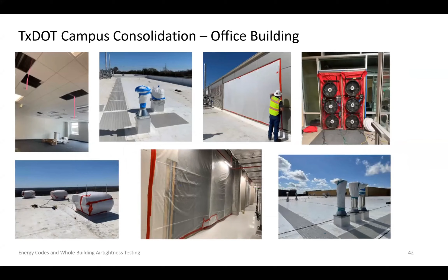So this is one where originally it was going to be divided into two zones, a zone A and B and a zone C. What had changed from the original bid documents we'd been given to prepare, compared to the as-constructed conditions, was that they had a huge pass-through on each one of these floors. So we had to do a bit of scrambling, but we already had sufficient fans on site, so we could pressurize this entire building, and it came out at 0.121 CFM 75.